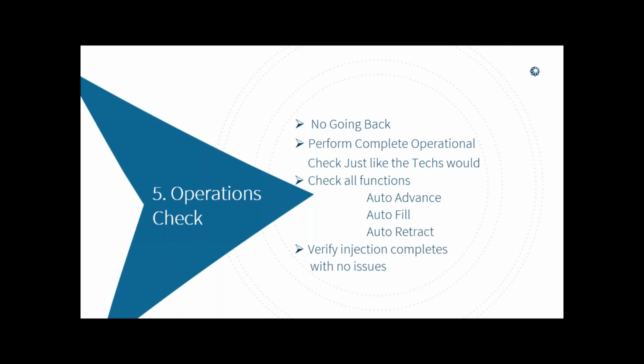Whereas if you did an operations check, you would find that the fill B side was not working. But you must have done something to it, because it was working fine. But they didn't tell you they ran the injector into the other cabinet, the corner cabinet, and busted that button out. Oh, never happened. So now you have to fix it, because you broke it. You didn't, but you didn't do an operations check to find out.